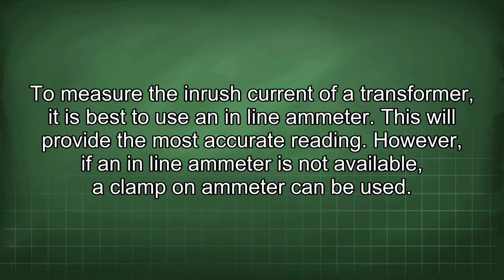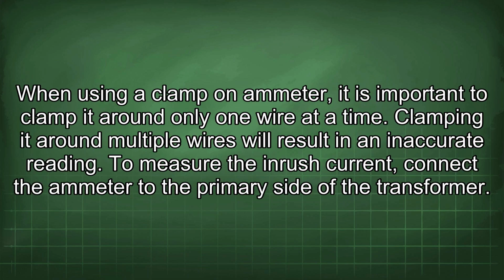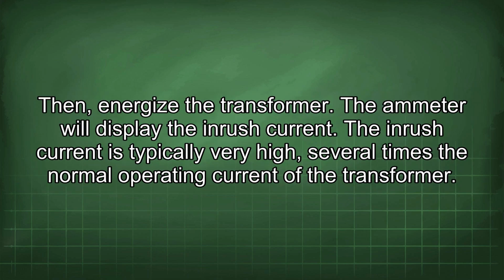To measure the inrush current of a transformer, it is best to use an inline ammeter. This will provide the most accurate reading. However, if an inline ammeter is not available, a clamp-on ammeter can be used. When using a clamp-on ammeter, it is important to clamp it around only one wire at a time. Clamping it around multiple wires will result in an inaccurate reading. To measure the inrush current, connect the ammeter to the primary side of the transformer. Then energize the transformer. The ammeter will display the inrush current.